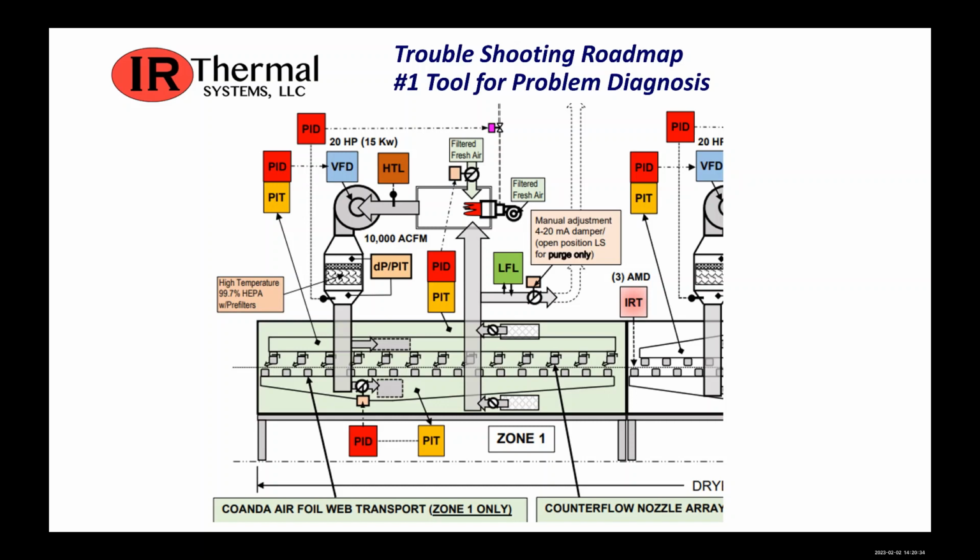Their heater was maxed out, they had about a 240-degree delta of the air across the heater, as well as their VFD was maxed out. So the system could not be turned up anymore. Using the P&ID, the next variable I had to work with was the fresh air coming into the system. Now, this is, of course, ignoring a major rebuild or redesign of the heat system. So without being too intrusive into their operation, we figured out that they had 60-degree air coming into this system.